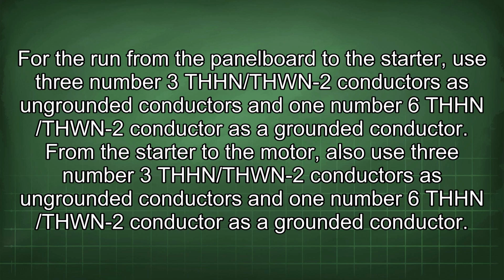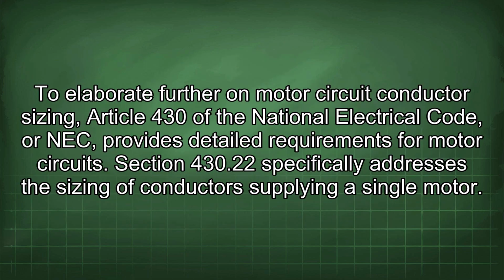From the starter to the motor, also use number 3 THHN/THWN-2 conductors as ungrounded conductors and number 6 THHN/THWN-2 conductor as a grounded conductor. To elaborate further on motor circuit conductor sizing, Article 430 of the National Electrical Code, or NEC, provides detailed requirements for motor circuits. Section 430.22 specifically addresses the sizing of conductors supplying a single motor.